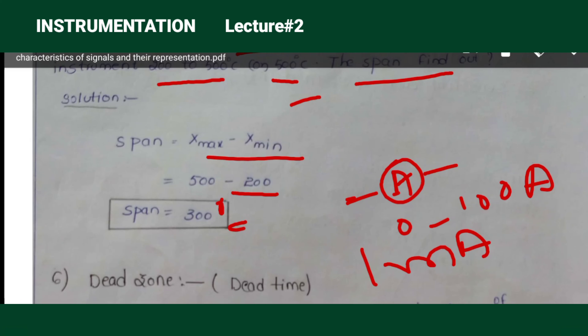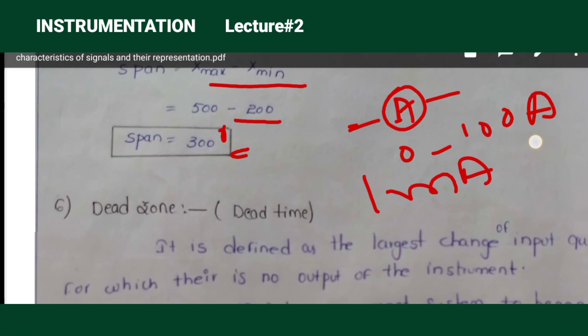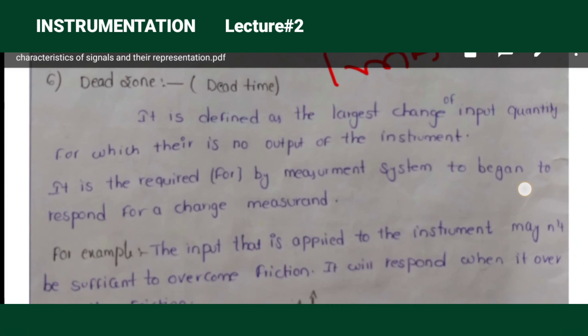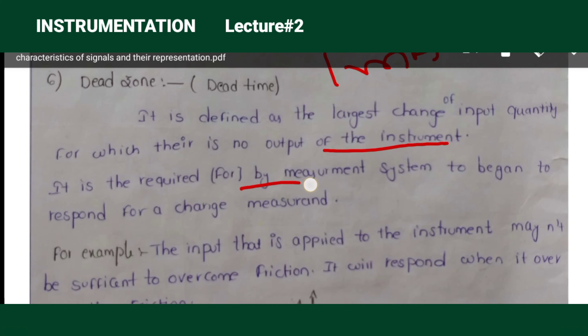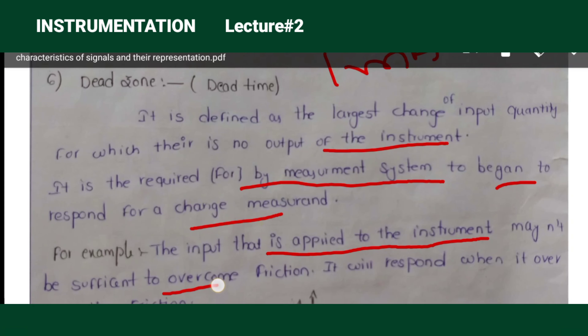Dead zone is defined as the largest change of input quantity for which there is no output from the instrument. Up to some incremental input, the measuring instrument will not begin to respond. For example, if you apply 1 milliamp to a 100-amp ammeter, it won't overcome the friction and losses — the instrument responds only when input exceeds the friction threshold.